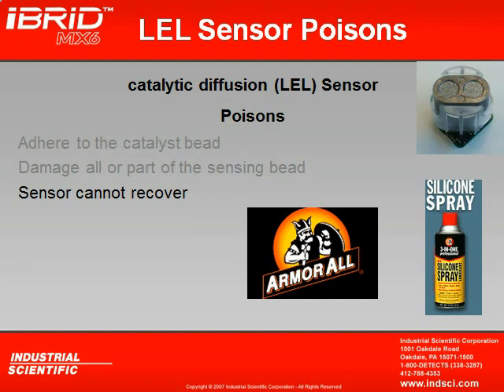It's permanent damage. So we always recommend that if you think you've exposed the sensor to an agent like silicone, that you should calibrate it. The reason you should calibrate the instrument is twofold. One, you want to ensure that the sensor is still working, and two, previously we talked about full spans, and a full span gives us an indication of the strength of the sensor. If there's a big difference in full span between one calibration and another, it could be an indication that the combustible sensor was exposed to a poison.